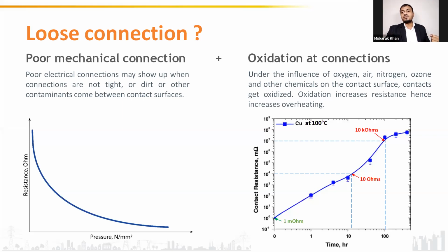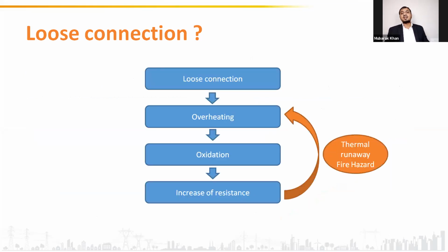Or it can be because of oxidation at the connection. Under the influence of oxygen, air, nitrogen, ozone and other chemicals on the contact surfaces, the contacts may get oxidized. Oxidation increases the overheating, which can cause further damage. As you know, the resistance of copper oxide is much higher than the copper itself. That is why there is localized overheating in this scenario. Let us take an example of a sequence of events which happen under the scenario of loose connection.